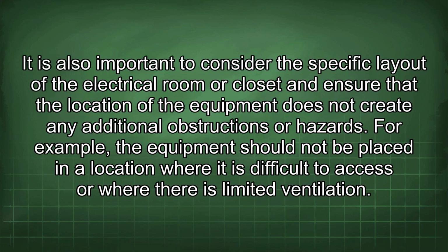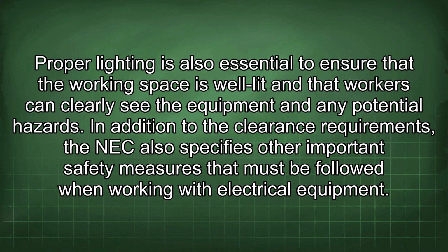It is also important to consider the specific layout of the electrical room or closet and ensure that the location of the equipment does not create any additional obstructions or hazards. For example, the equipment should not be placed in a location where it is difficult to access or where there is limited ventilation. Proper lighting is also essential to ensure that the working space is well lit and that workers can clearly see the equipment and any potential hazards.